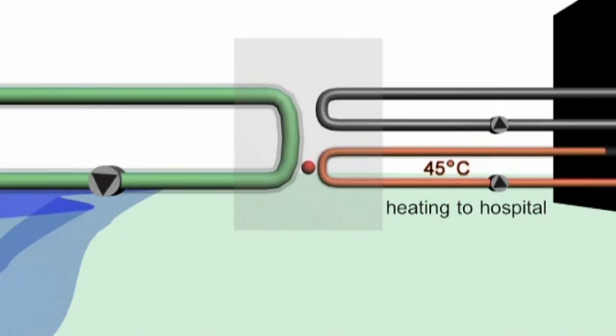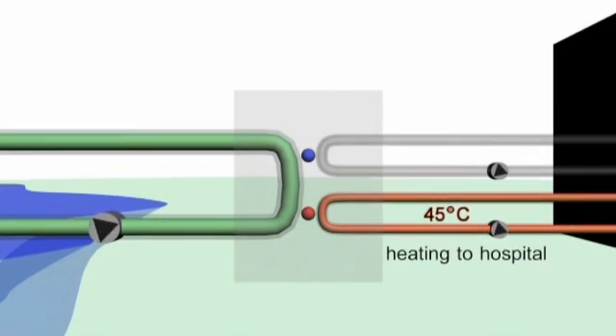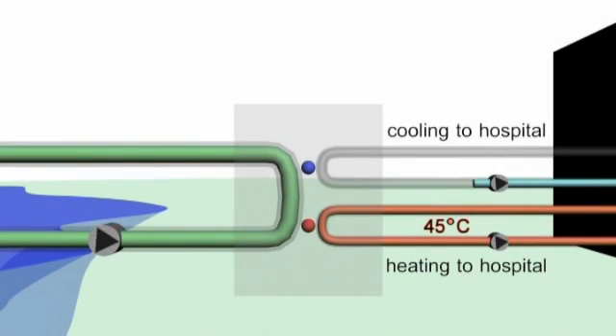It preheats the feed water to the hot water service calorifiers and steam plant, which provide the building with air heating. In reverse, the pumps add heat pulled from the building to the pipes, which is returned to the reservoir. This provides chilled water at 6 degrees Celsius for space cooling through local fan coil units and by cooling the fresh air supply within the hospital.